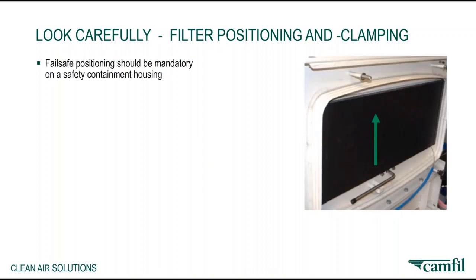When you are interested in investing in a housing, you should have a close, careful look. Remember, with a housing like this, you would typically be working under containment level L2 or even L3 with potentially toxic substances in the process air. So fail-safe positioning should just be mandatory.